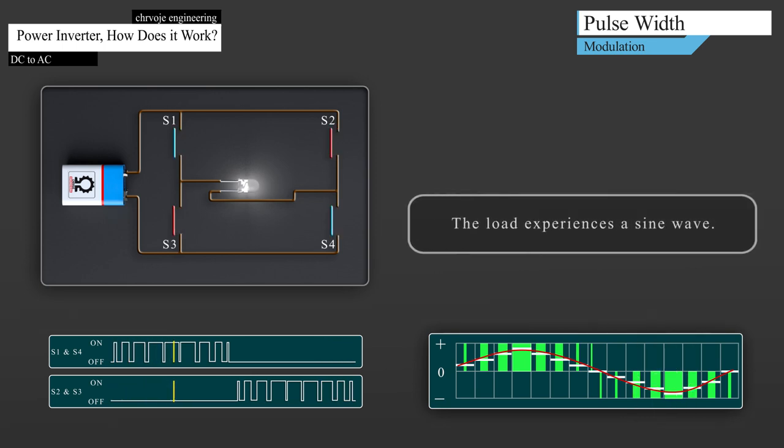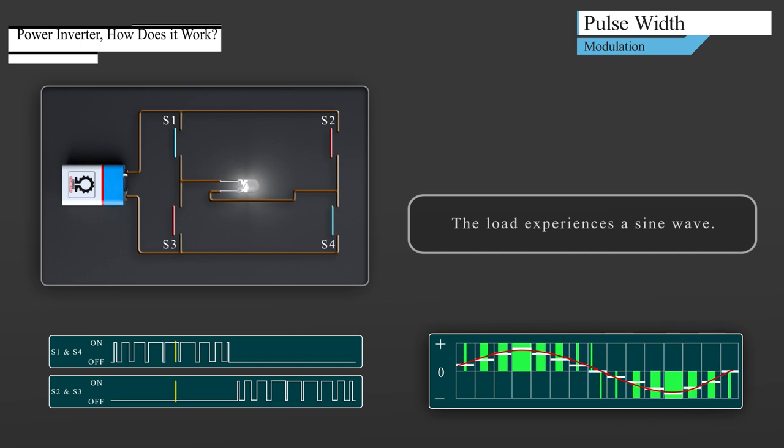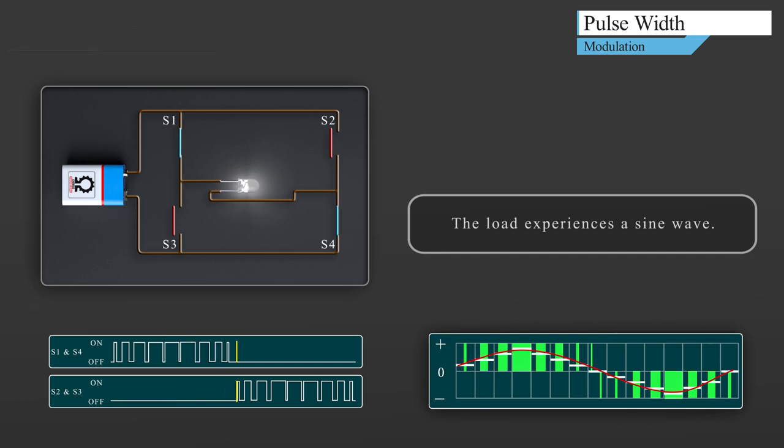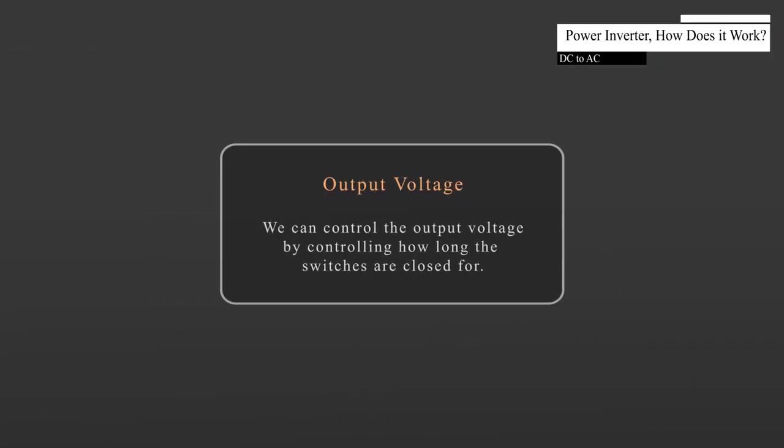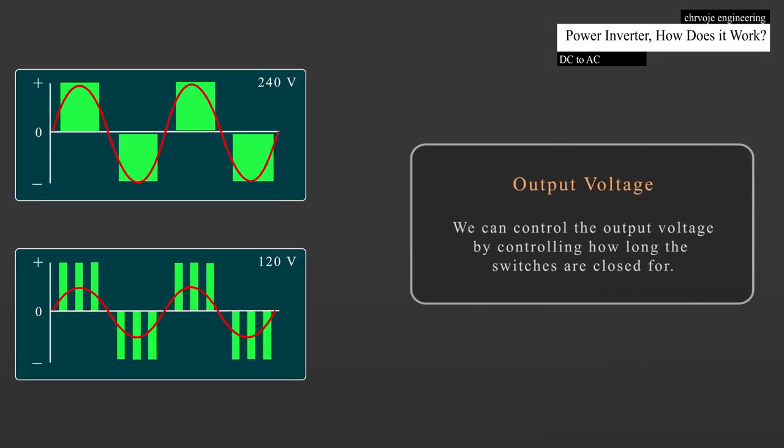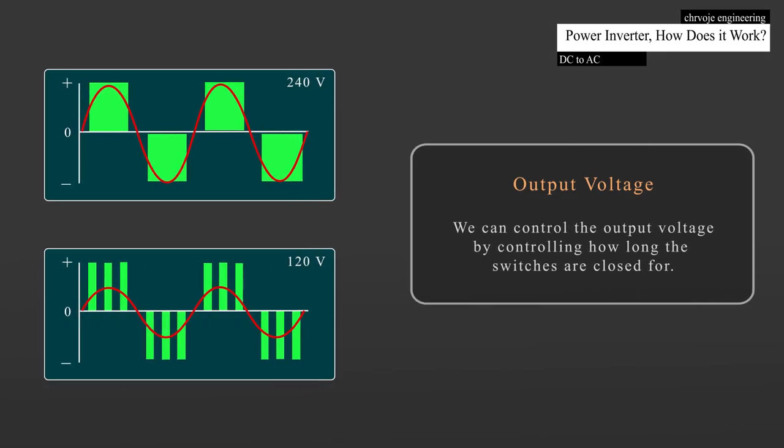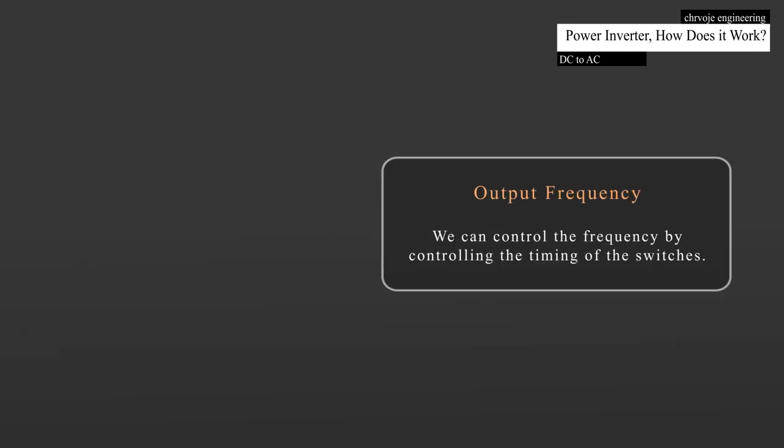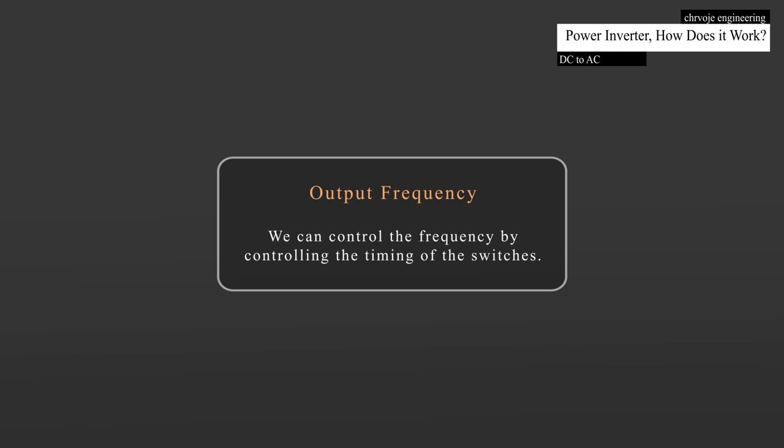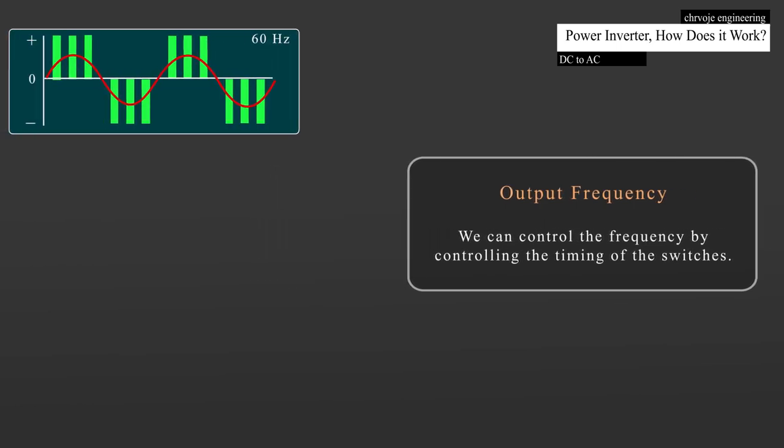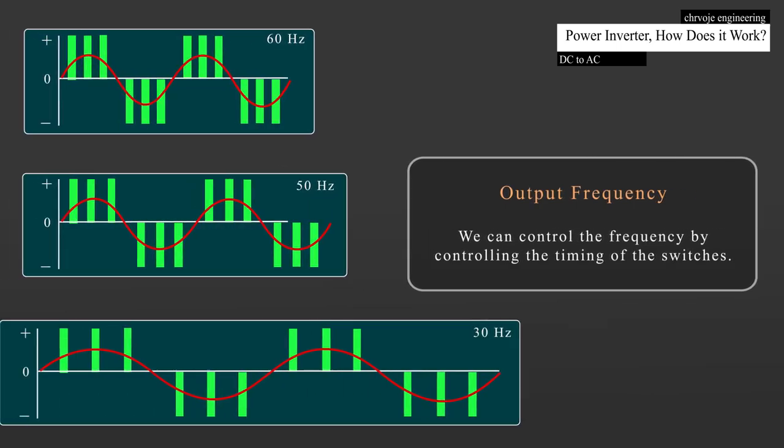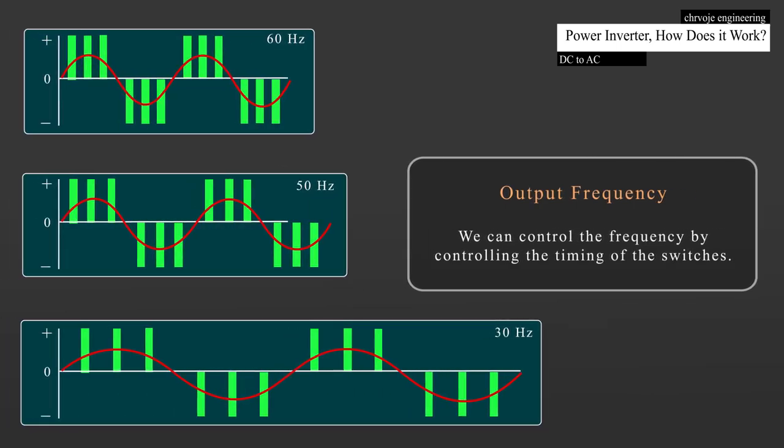So, the load will therefore experience a sine wave. The more segments we have, the sine wave will be smoother. We can control the output voltage by controlling how long the switches are closed for. So, we could for example have an output of 240V or 120V just by trimming the opening and closing times. We can also control the frequency by controlling the timing of the switches. So, we could for example have an output of 60Hz, 50Hz or 30Hz, whatever is needed for the application.